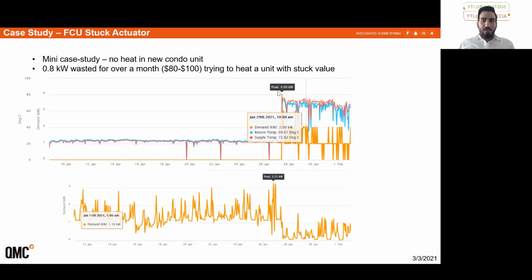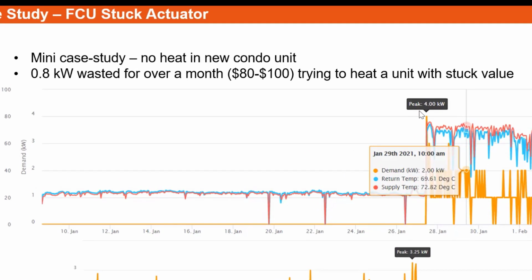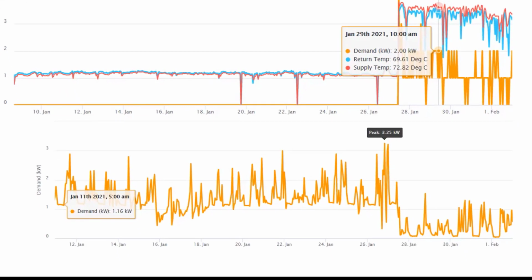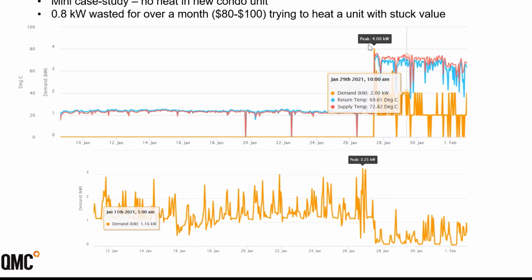Another example is a case study tracking thermal energy consumption. On the top graph, we're looking at data extracted from the BTU meter, or thermal meter, within the fan coil unit. On the bottom graph, we're looking at electrical consumption within the same suite. Drilling into the top graph, we're extracting supply and return temperature with flow rates, along with demand in kilowatt hours - the red and blue lines represent the supply and return temperature overlaying each other, along with a relatively flat thermal energy demand. When we overlaid this with the electricity consumption in the same suite and analyzed the data, we realized the actuator within the fan coil was stuck.